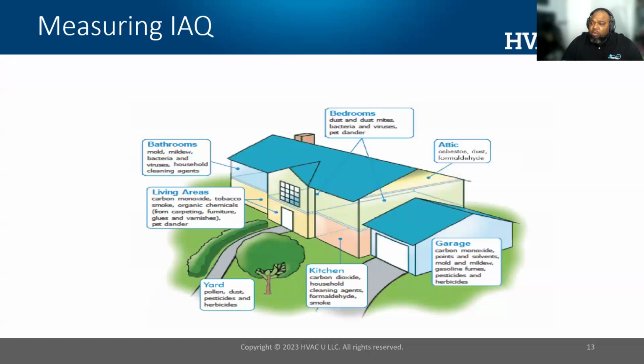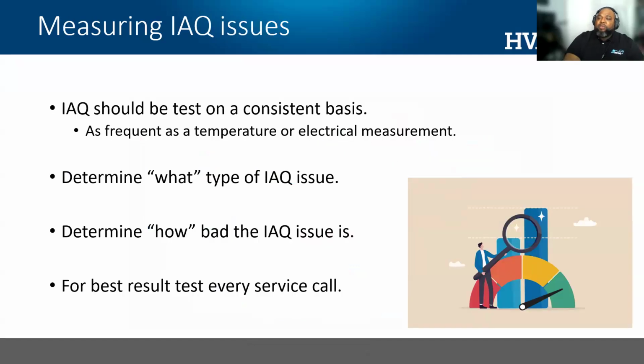All right. So measuring IAQ, there are a ton of factors that we're going to talk about, and they can come from inside the house or outside, and we'll distinguish those. But sometimes things in the house can contribute to these IAQ issues. Next, we're going to transition to measuring it and understanding what the problems are. So, big picture, the key takeaway is that measuring IAQ should be as common a measurement as temperature or electrical. As an HVAC technician or energy auditor, if you're running a blower door, measuring IAQ should be very commonplace. The reason is that it determines what type of IAQ issue you have and how bad it is. What's the magnitude? And to get an effective IAQ program or robust business segment, you should test on every service call that you have.